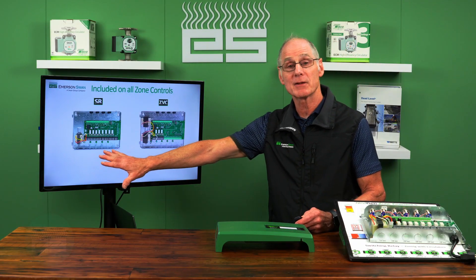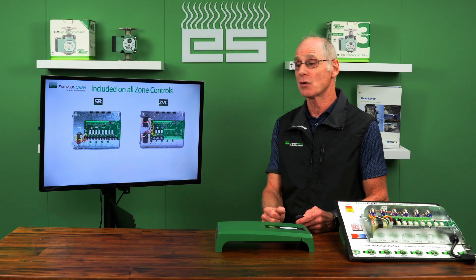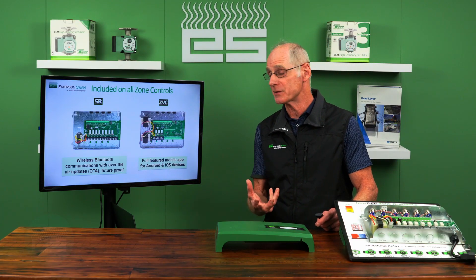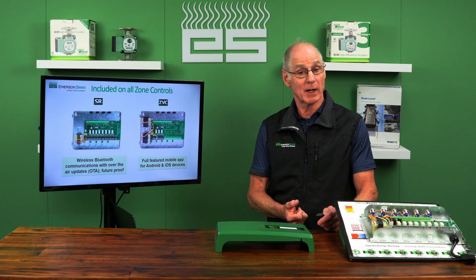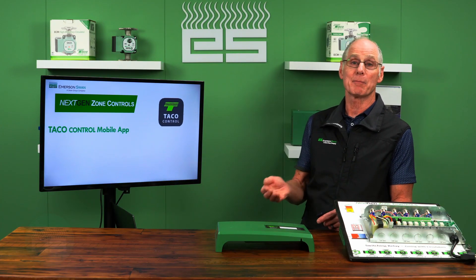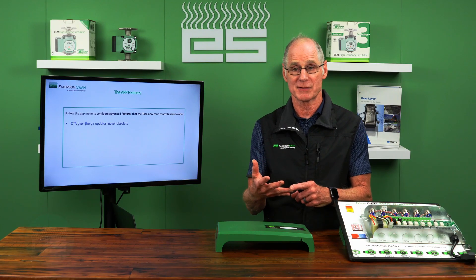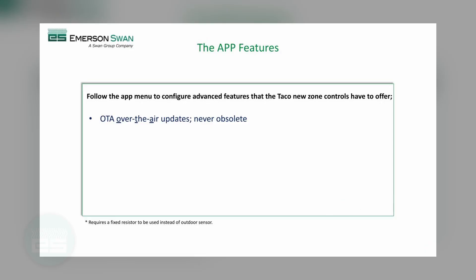It's the multi-zone models only — zones two through six on circulators and three through six on zone valves — but all those multi-zone products have Bluetooth built in. You can download the app for free. At no cost, I can get in there and configure that control for my job. The app is called TACO Control, available for iOS and Android. It's a configuration tool — I don't need Wi-Fi, I don't need cellular service in the mechanical room. I'm talking Bluetooth between my mobile device and the control.